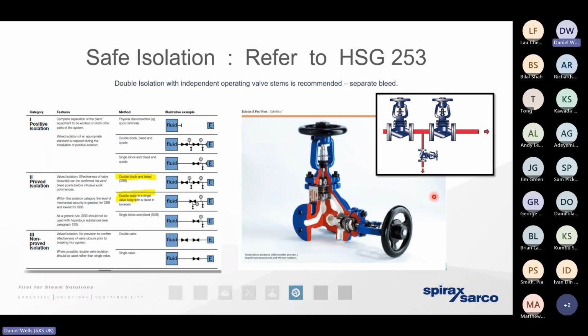And if this telltale is bleeding away to a tundish in the corner of the plant room, flash steam emissions that are wisping away from the corner of the plant room give us a visual indication. They give us a telltale to advise that that primary valve is passing, but most importantly, it gives us peace of mind that we're working on that heat exchanger on that process safely. The thing to bear in mind is safe isolation or double block and bleed on steam systems is not mandatory. It is just guidance. Some clients will insist upon it and others won't be bothered.